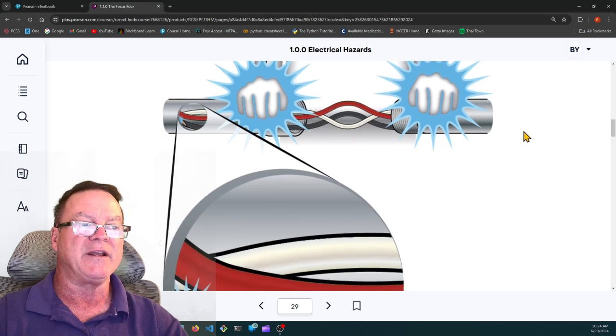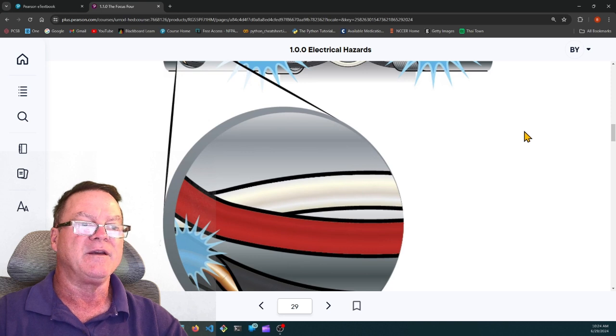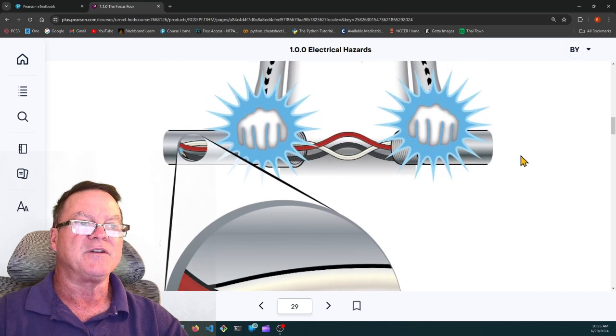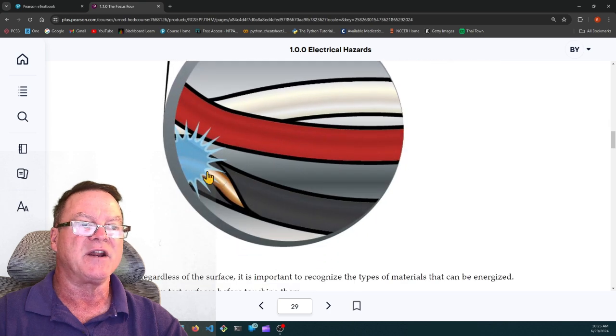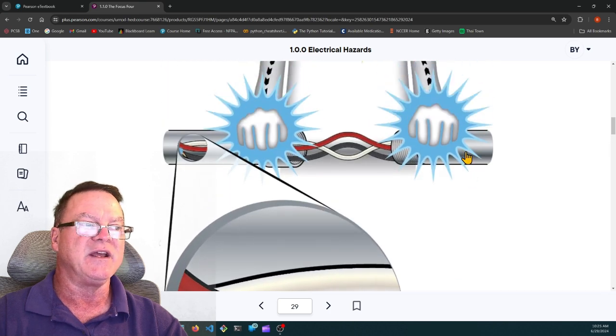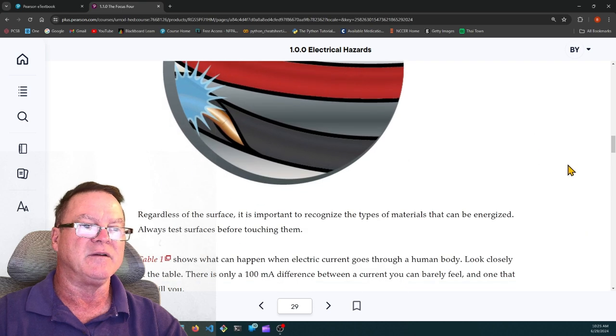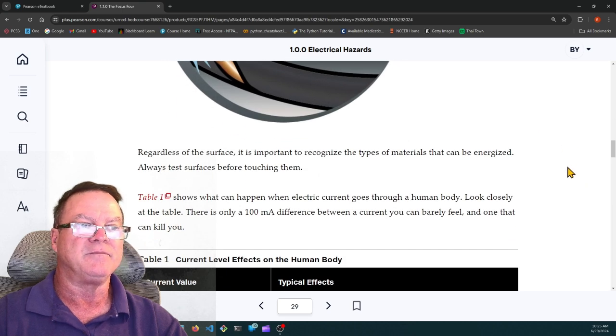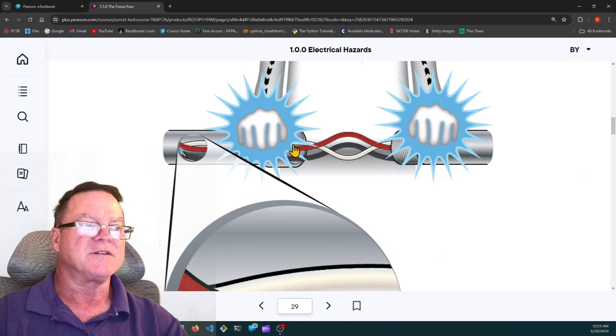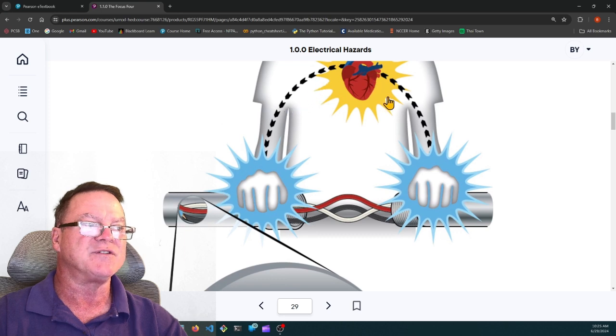Not sure exactly what they're showing, but they're showing that there's a short in one of the wires and it's touching the side of the conduit, so the conduit is electrified. The worker didn't know it, and they grabbed onto the pipe and got electrocuted. Actually, it's when they took the pipe apart, they unscrewed the coupling and pulled the pipe apart, so now the only path for that electricity is to go through the person.